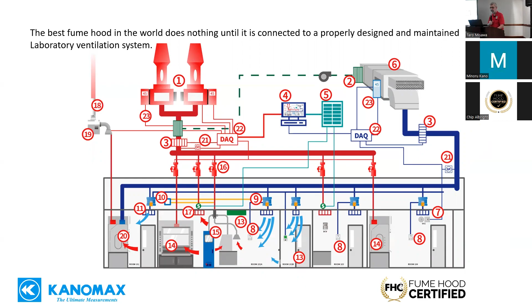Face velocity is not an indication of containment. In reality, if you do a face velocity reading of a fume hood, all that's telling you is that the air is going in at a certain speed. It's not telling you what's really happening, and we're going to look at that in a little more detail. Interestingly enough, about 70% of the hoods that fail safety containment have an acceptable face velocity. So there's no direct relationship. Face velocity is a component of containment, but it's not an indication.